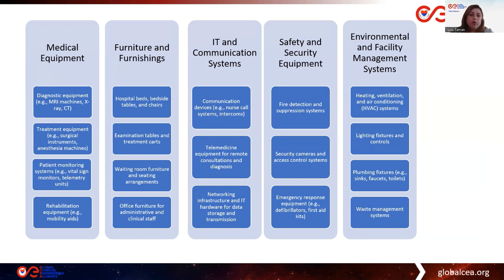patient safety. Also, around cybersecurity, which is less understood or less effectively managed around medical equipment in a hospital, there is a very good understanding around cybersecurity and IT equipment. But medical devices have their own intricacy around cybersecurity, where you cannot implement the traditional cybersecurity solutions on medical equipment. Again, it's very important for a clinical engineer to be involved to highlight the needs and the challenges around those cybersecurity, and ensure that effective security is put in place.